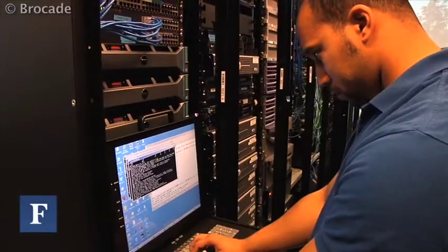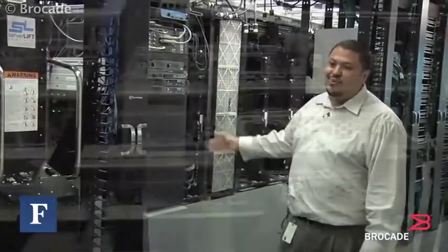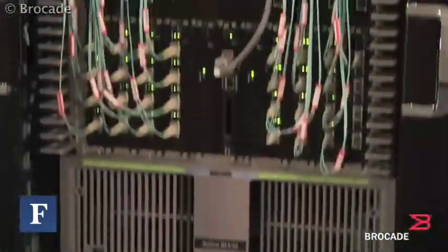How did you discover this was going to work for you? There's been a lot of industry work on looking at the major costs inside a data center. This was a project we took on with a couple of partners and mechanical engineering firms in San Jose, and we custom designed some of these in-row cooling units. It's such a big piece of the cost in the data center. We took about 37% of our power usage out of our data center.